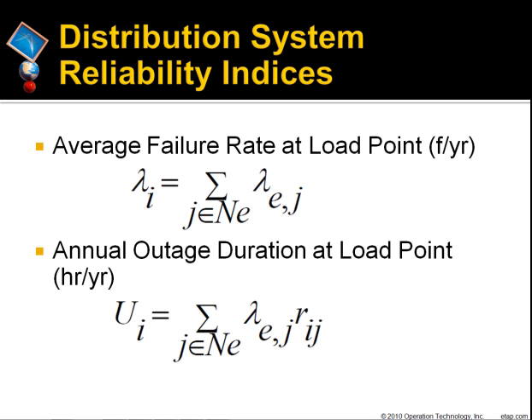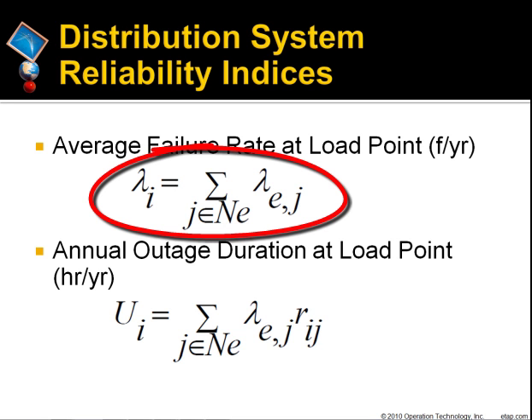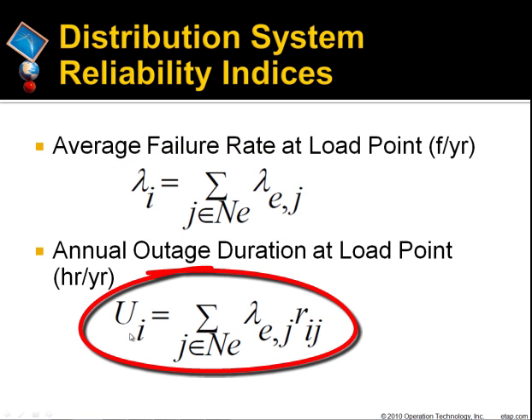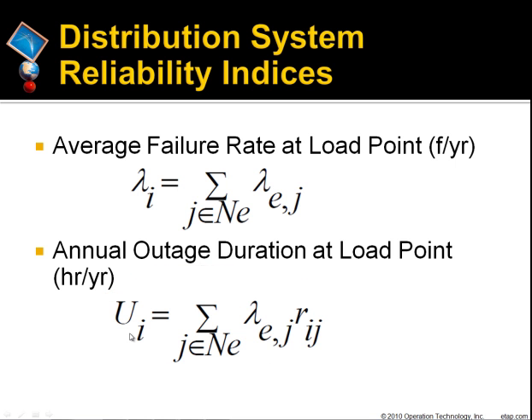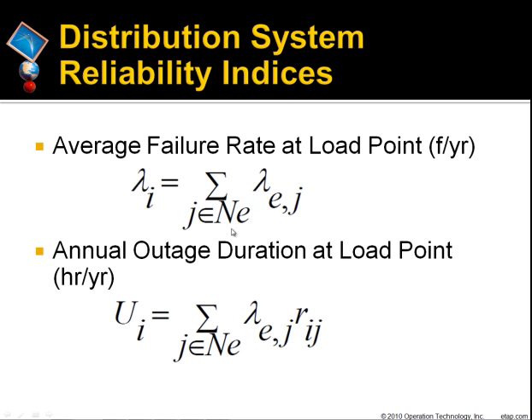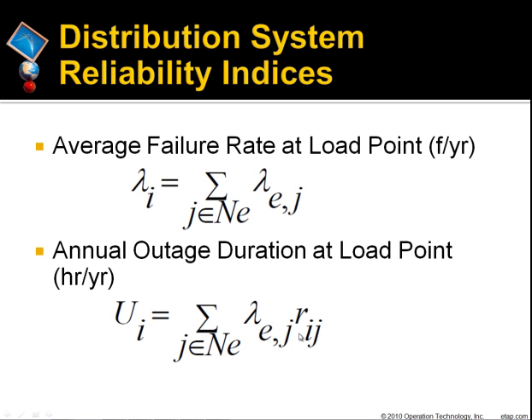Now let's summarize the most common distribution system reliability indices. The average failure rate, lambda i, and annual outage duration, u_i, at load point i are calculated by these equations, where lambda_e,j is the average failure rate of element j or element combination j such as double contingency, and Ne is the total number of elements whose faults will interrupt load point i. R_i,j is the failure duration at load point i due to the failure of element j.